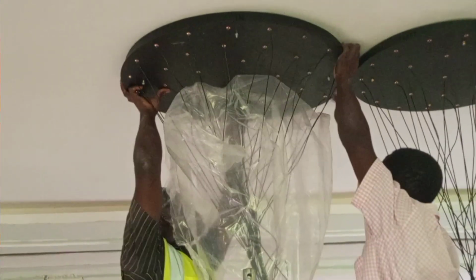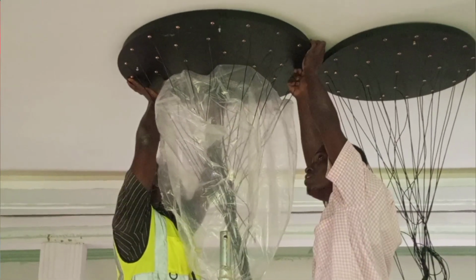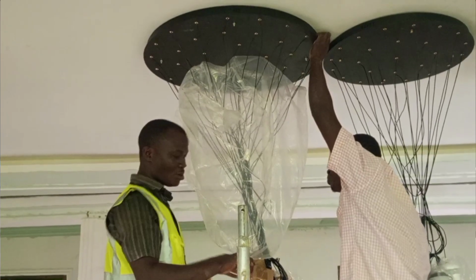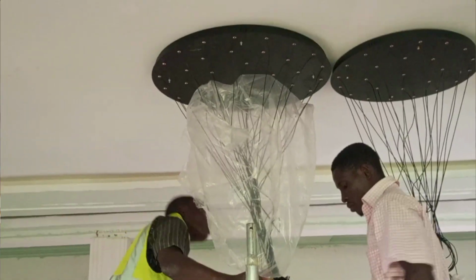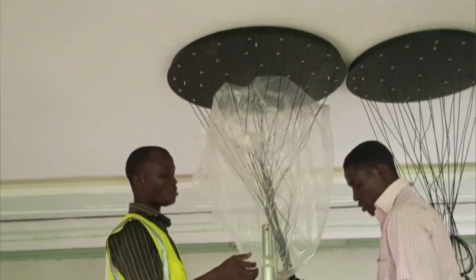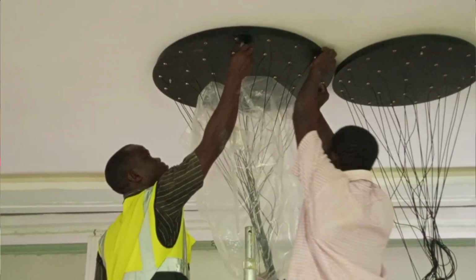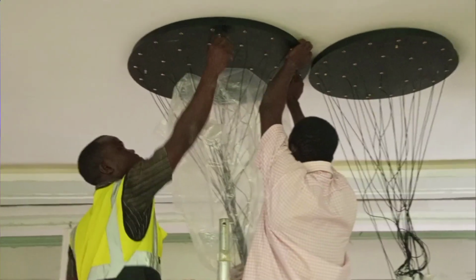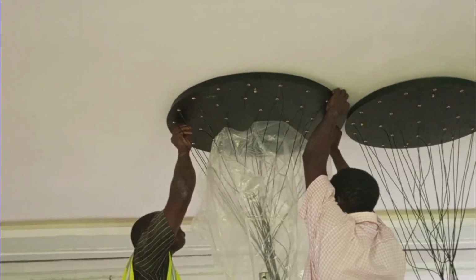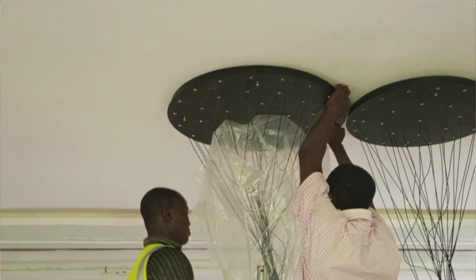Okay, now these two are already 10 amps and the wiring has already been done with 1.5 millimeter squared cable, and that can safely withstand 10 amps. And then we are putting only these two lamps in one circuit and then protect them with a 10 amp breaker. So anytime more current than 10 amps wants to flow in this circuit, the breaker would have to trip, and that is perfect.